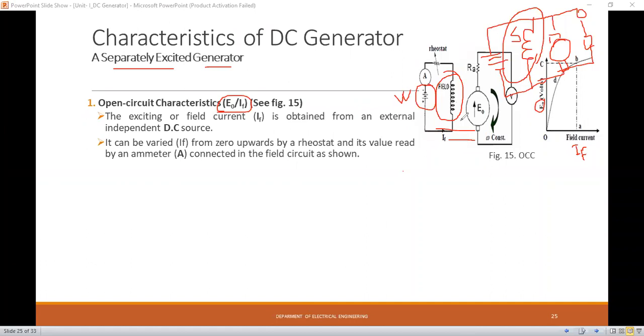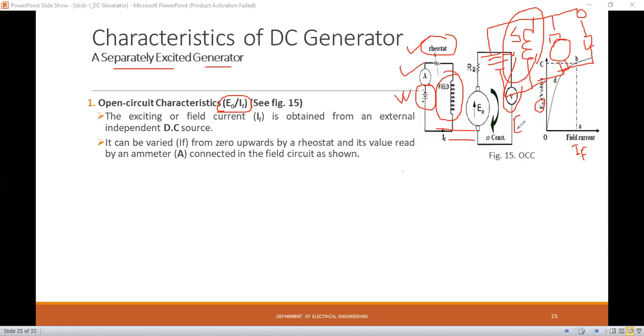By reducing the resistance of the rheostat, the current flowing through the field winding is increased gradually. To measure the voltage induced at no-load condition, the output terminal is kept open-circuited and a voltmeter is connected to measure the induced EMF E0. If the E0 versus IF values are plotted on a graph, we get the open circuit characteristics.